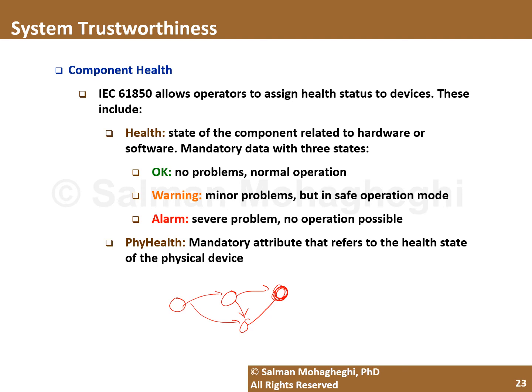Luckily for us, IEC 61850, which is a very important standard related to utility automation systems, defines some attributes for individual objects, physical or logical objects, so that we can identify either the physical health of different components or the integrity of the data or services that are provided by them. One, for example, is the logical node health. Within the context of IEC 61850, this is known as the logical node, but you can think of it as an attribute associated with that particular component. One is logical node health, and the other one is physical health.